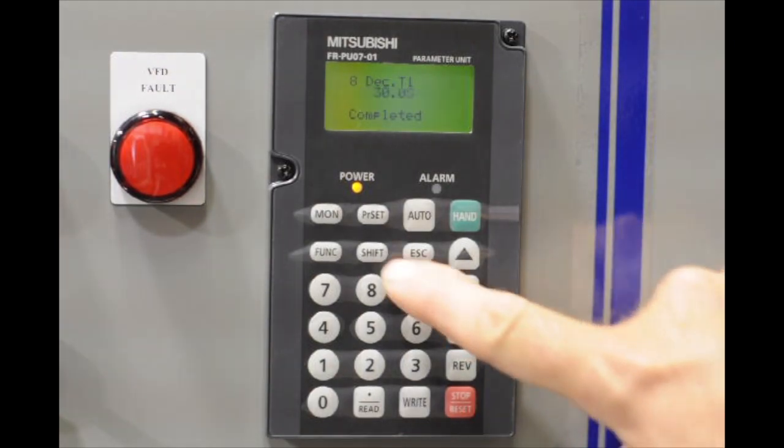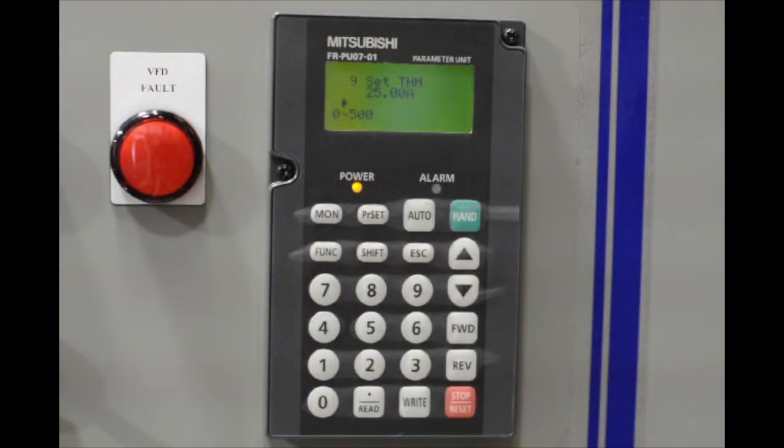Now, we're going to move to parameter nine by pushing shift. This is where we put in the thermal value of your motor. Whatever the current rating of your motor is, we're going to go ahead and type it in here. Let's just say your motor has a decimal place point like fifteen point nine.